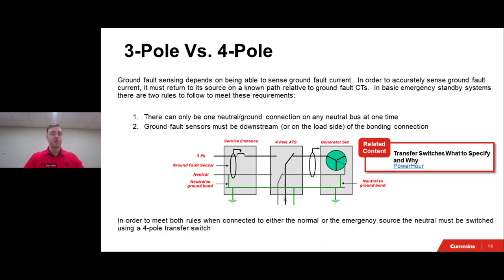Next, I will briefly cover three pole versus four pole transfer switches and the differences between the two. So the differences between a three pole and a four pole transfer switch are that a three pole transfer switch has the three phases of A, B, and C, and a four pole is switching all three phases and having that neutral ground neutral together simultaneously. So if the ground fault protection is needed for your application, then you will need to use a four pole transfer switch.